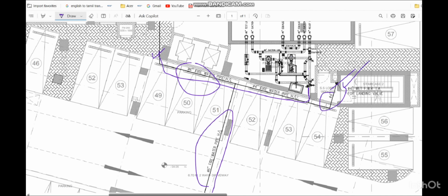This is serving only the landing valve. But here the mistake is that this line which is coming and which is distributed like this: here it is 6-inch, here it is 6-inch, and the main distribution line here is shown as a 4-inch, which is not correct, because here it is 6-inch, so this has to be the higher size. This is shown as a 4-inch, it has to be 6-inch only. So this is the second mistake for this project. We updated this one in the next stage.